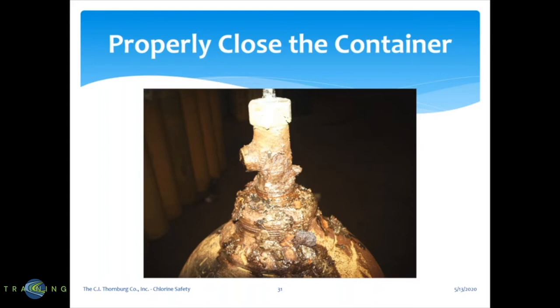This particular cylinder was not even closed. There is still residual gas in these cylinders once they're deemed empty, and this is what happens — it corrodes the valve, runs down the side of the cylinder, and makes a real mess. We need to return those cylinders to our supplier in good condition. Just make sure the valve is closed on the cylinder once you're done using it.